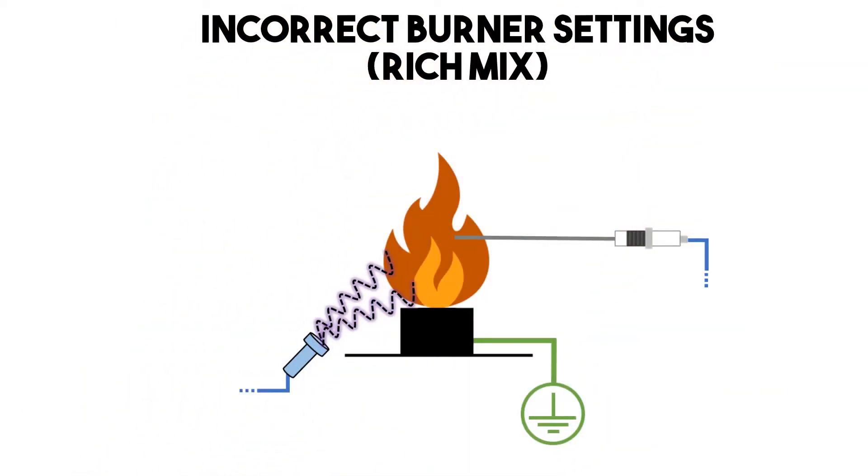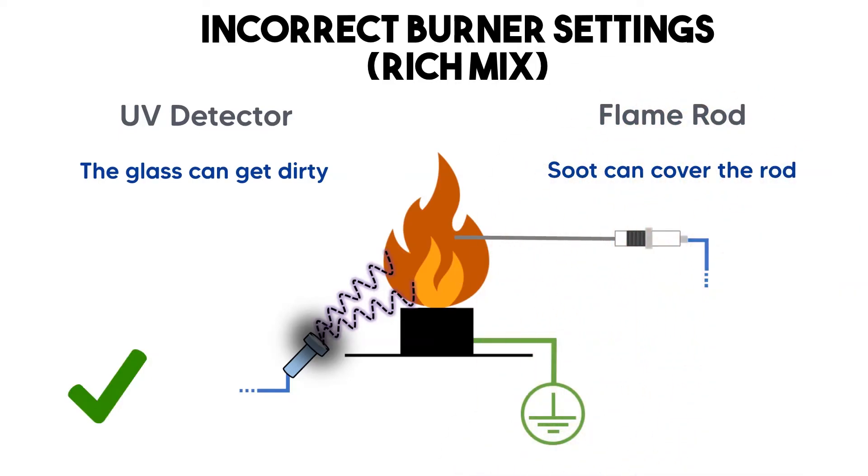Incorrect burner settings with a rich air gas mixture. The UV detector glass can get dirty with soot but it does not affect it significantly. For the flame rod the soot caused by carbon buildup can cover the rod resulting in a poor reading.